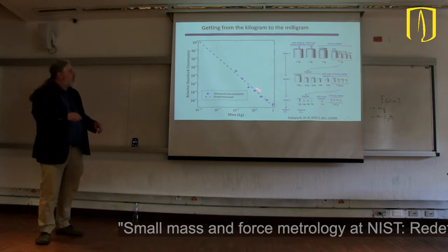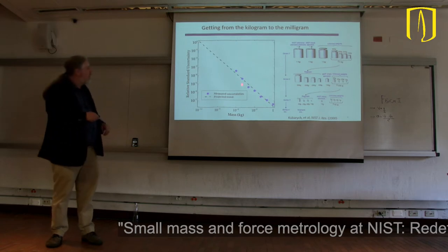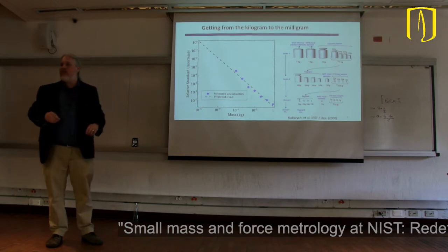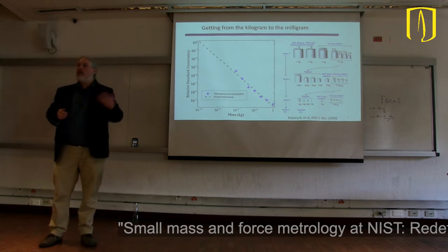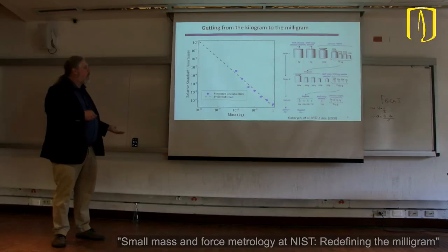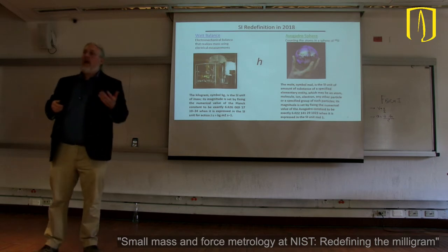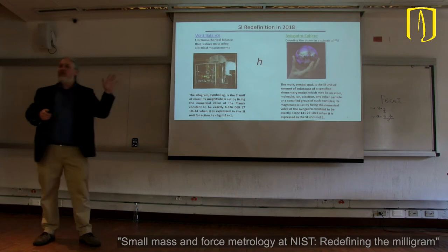If you extrapolate this linearly, which is a charitable assumption, you can see by the time you get down to nanograms, our measurement uncertainty is as large as the mass itself. So this is not really a sustainable measurement past a certain point. And we wanted to see what we could do to change that. Concurrently, as this idea was developing, something very big happened in the world of measurement.